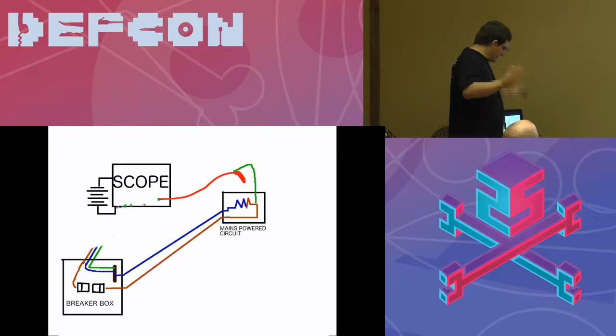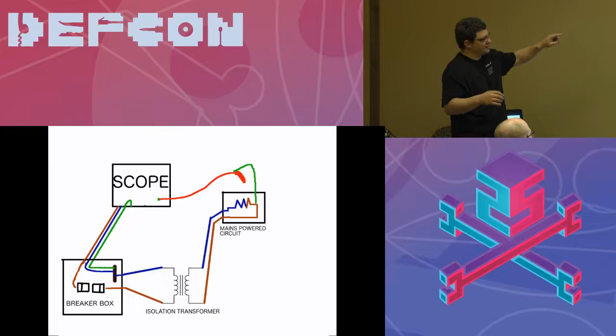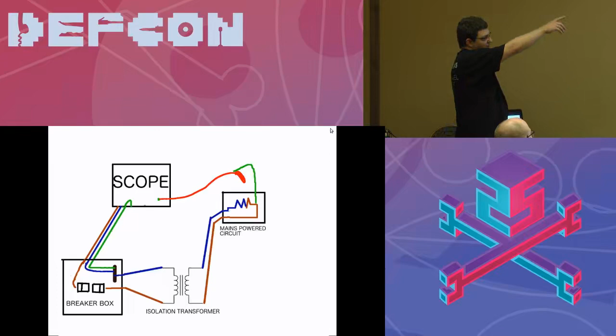Third option is isolation transformer. This only works if you are using a low-powered thing under test here, because an isolation transformer bigger than about 200 watts is huge. So generally for 200 watts or less, you can use an isolation transformer for the thing you're testing, and that isolates it as well. It breaks that path between the live and the ground.